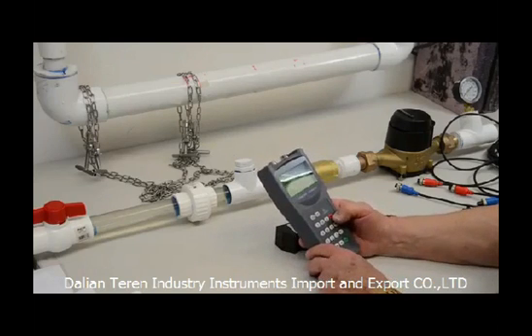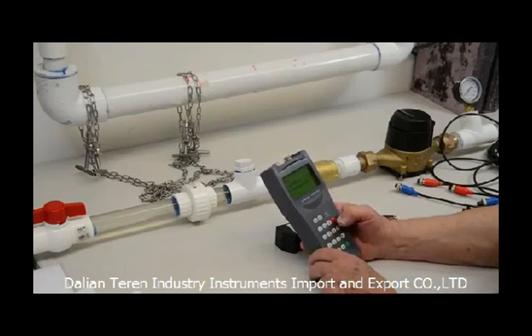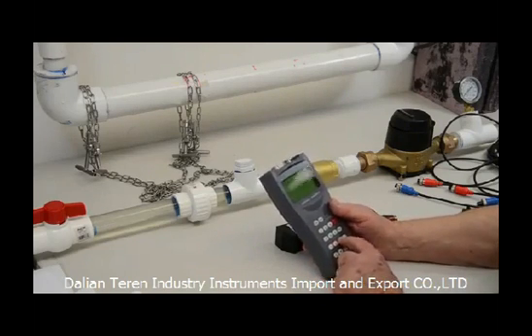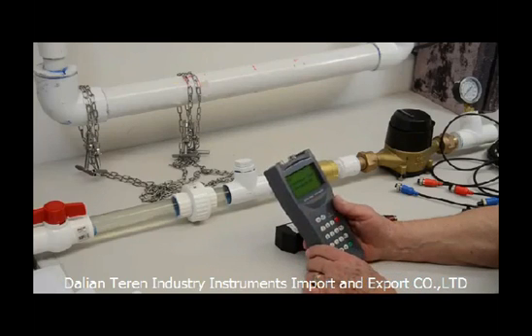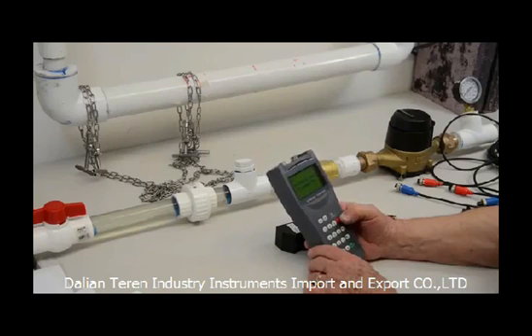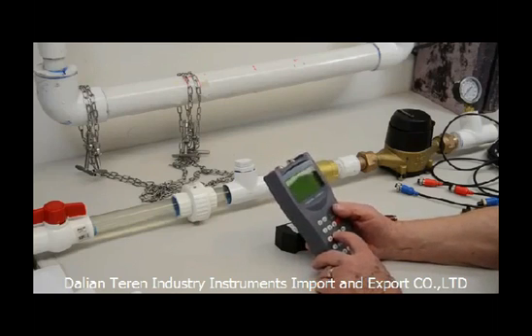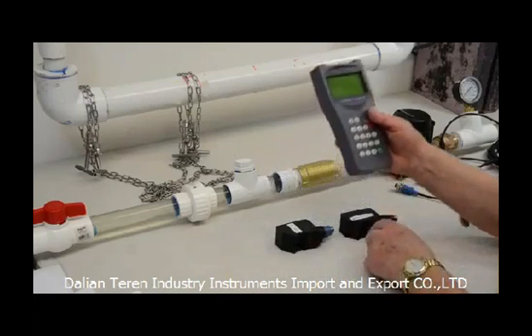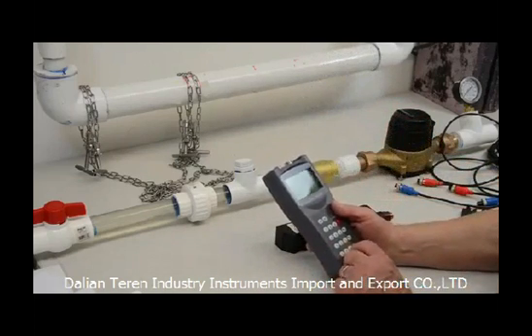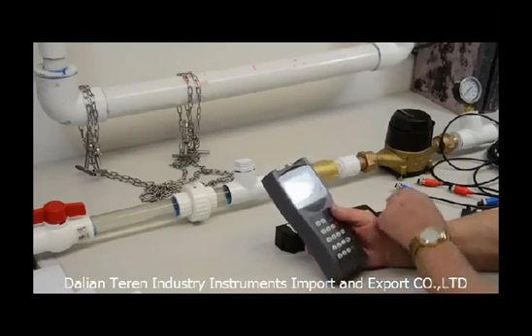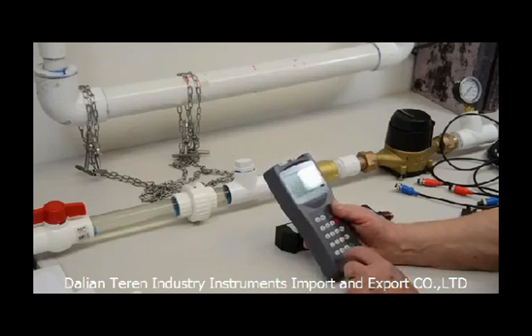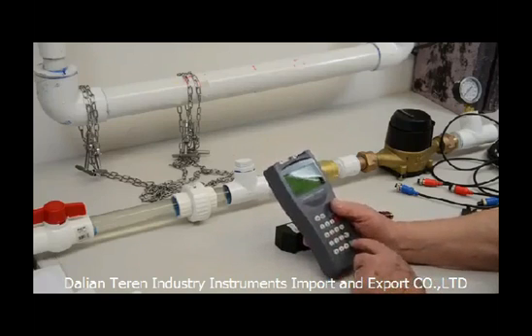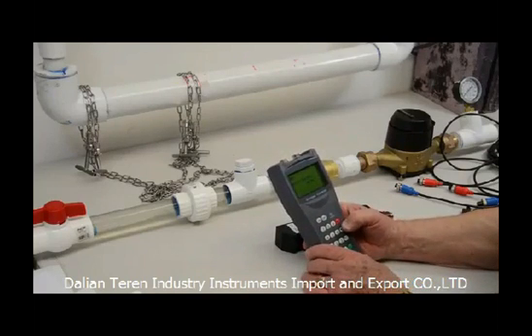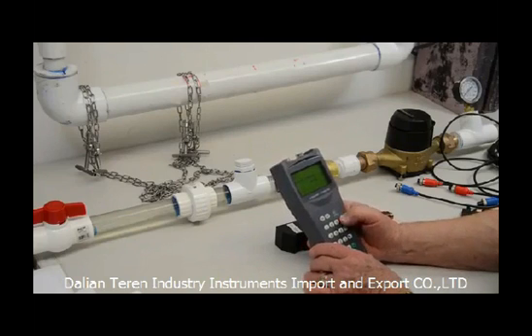The next step is to determine the transducer type, which I've selected in advance. So I push menu 2-3 and I select the transducer type. There's quite a few different transducers available. In this case, I've selected the standard M1 transducers. The next step is to do my scale factor, which is menu 4-5, and I know my scale factor because it's on the transducer, so I put in the scale factor, which in this case is 0.95, so 0.95, enter.